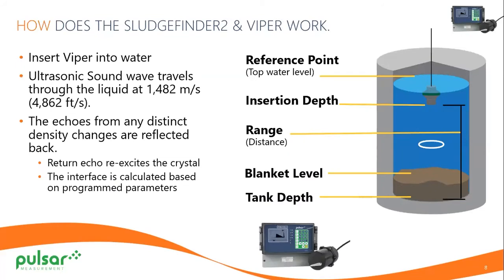How does the Sludge Finder 2 and Viper work? Well, we insert the sensor into the drink, and the sensor waves travel through the liquid at 4,862 feet per second. The sensor is 700 kilohertz, and that sensor fires and it bounces off of the blanket level. And if there is no blanket level, it will hit the bottom.